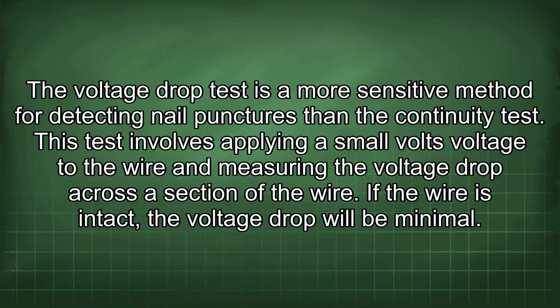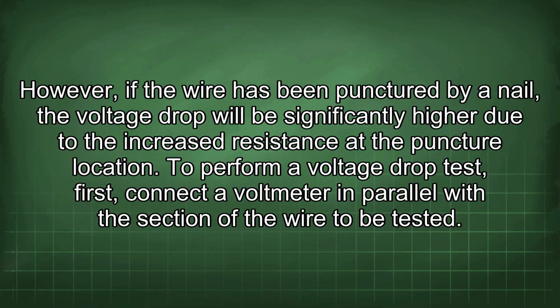The voltage drop test is a more sensitive method for detecting nail punctures than the continuity test. This test involves applying a small voltage to the wire and measuring the voltage drop across a section of the wire. If the wire is intact, the voltage drop will be minimal. However, if the wire has been punctured by a nail, the voltage drop will be significantly higher due to the increased resistance at the puncture location.